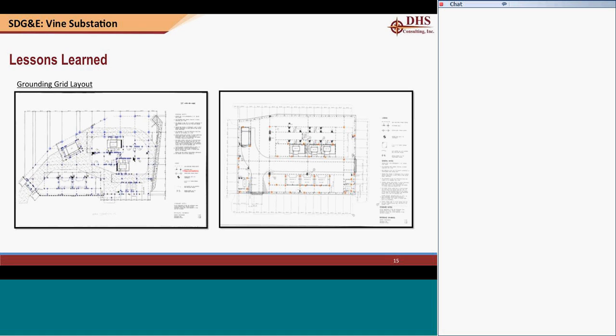In other words, it's not until you actually import all your soil for the first time that you're able to do a grounding grid study and check the conductivity. They put one probe in, another probe in, and they can tell how conductive the ground is. Based on that, they go back and design the grid.